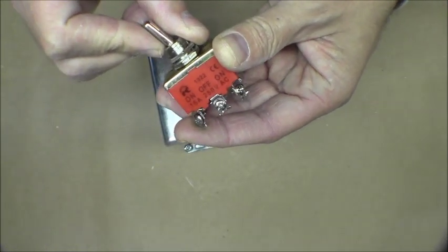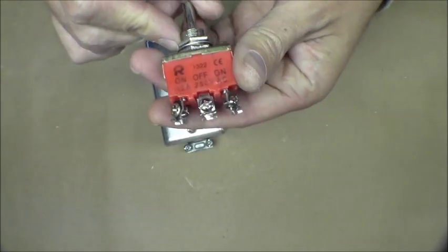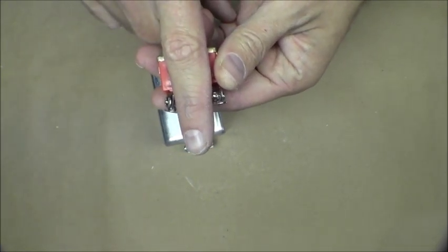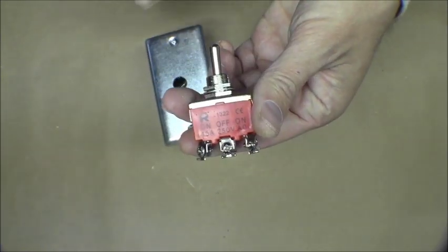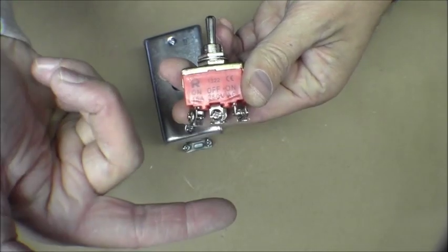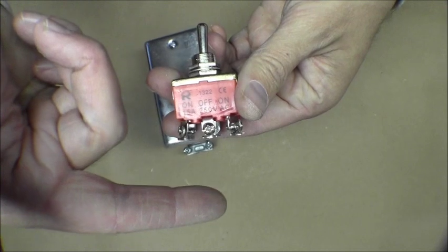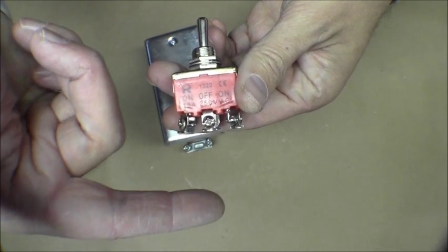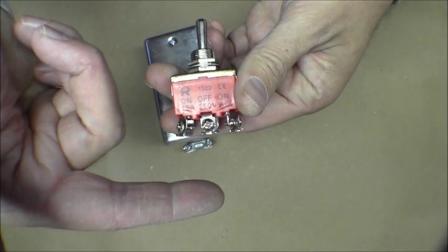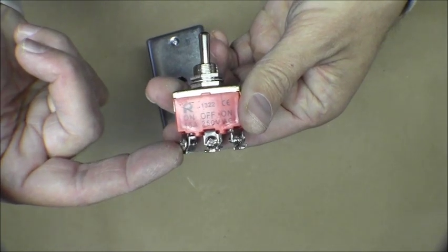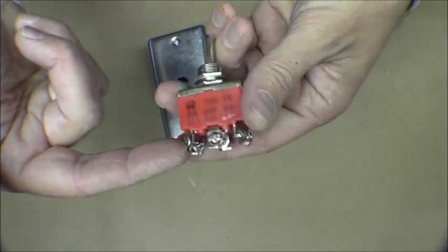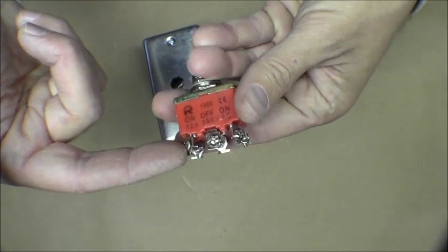It's real important you get a double pole double throw. What that means is that we've got a center pole which is our common, meaning it's always connected all the time. This is what's going out to what we're powering - say this is powering our gas furnace. So this is the power coming off, the leg coming off here is always connected to what we're powering.